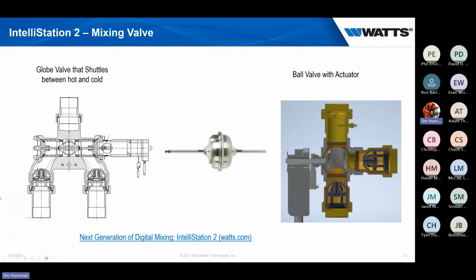So this is more of an internal view. As our water is entering, you're going to notice we have our check valves. You don't want to have a mixing valve designed without them, thinking you can get more water, because anytime you add anything into our piping system, such as check valves, you're going to have a little bit more pressure drop, but please don't design them without it. We'll have massive amounts of crossover.